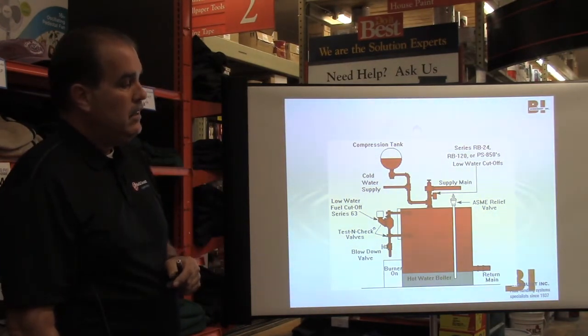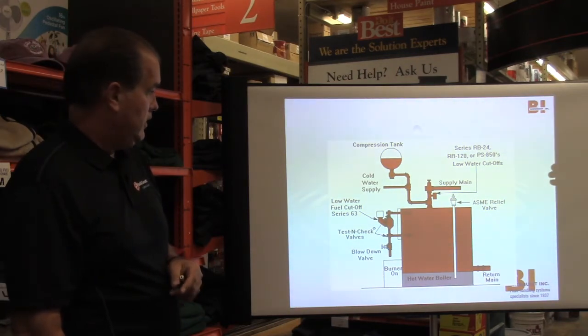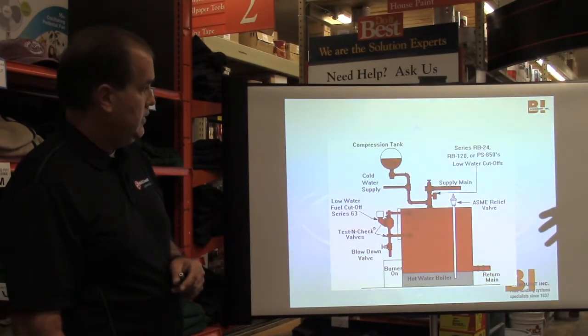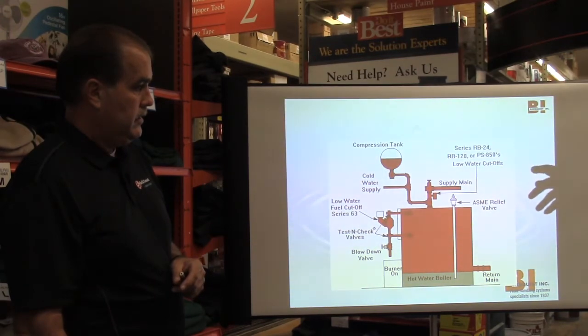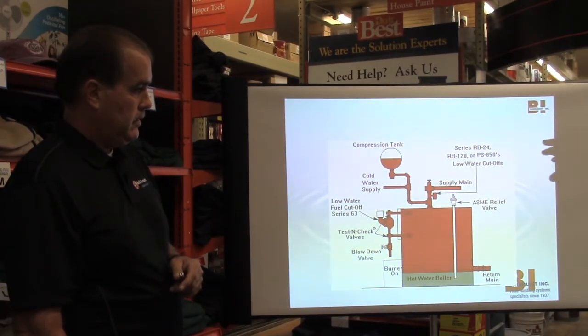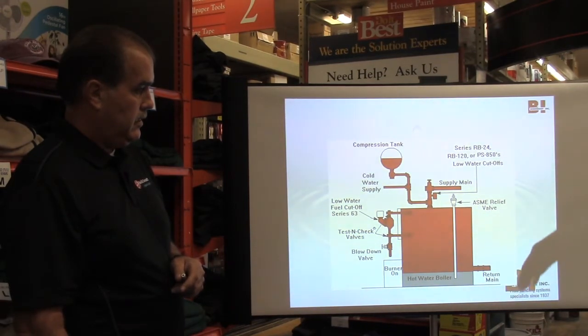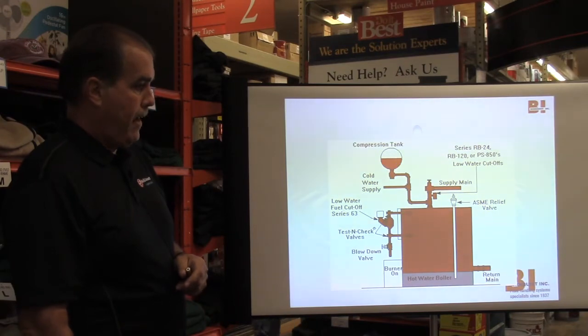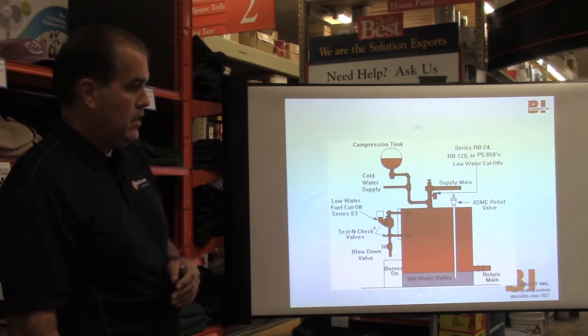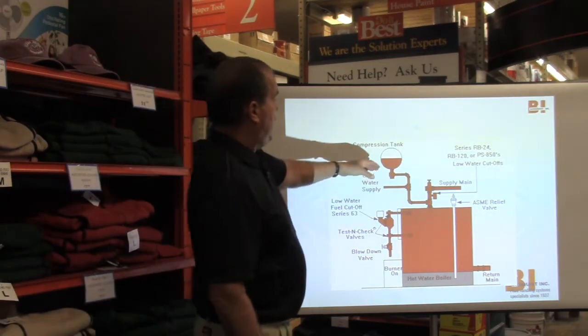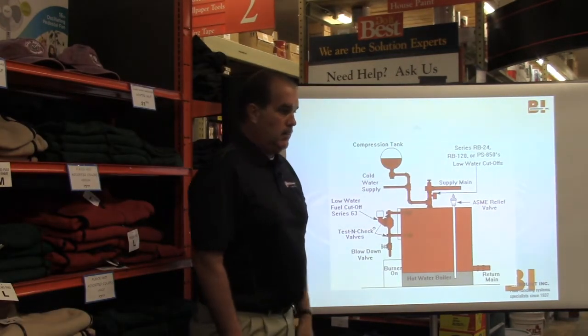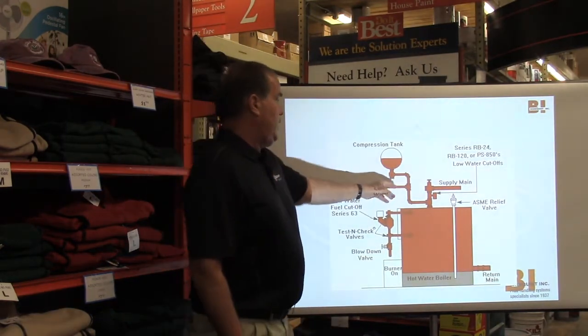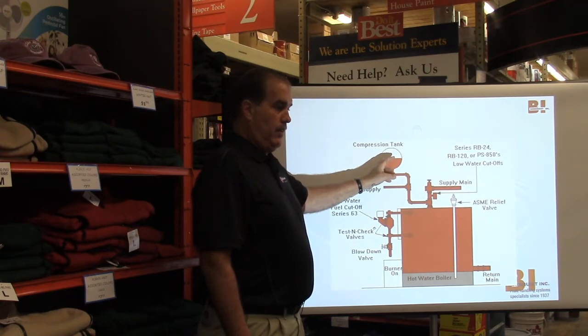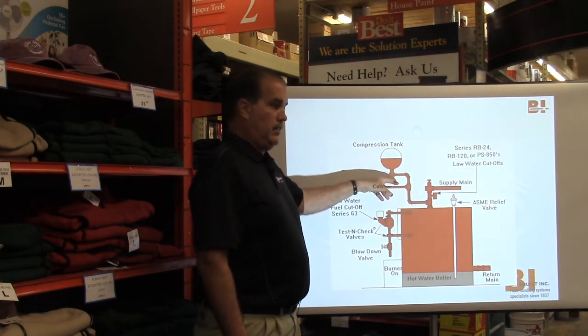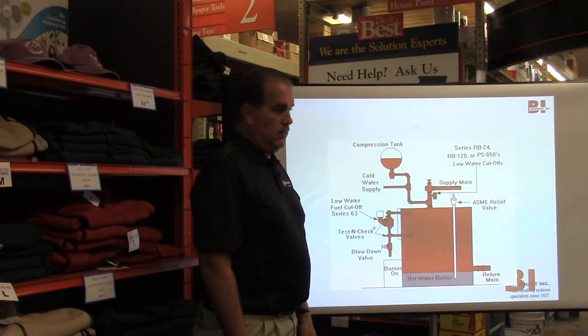Now, let's say I drain all the water from it, and of course I shut down the whole water supply and drain it completely. Then when I open up the water supply, and the water is drained in the tank, the water goes back into the tank. I can hear it. Yeah. That's normal? I thought something was wrong. No. The tank typically is going to be about half filled. That's okay. That's designed, and you might have a fitting that Bell & Gossett makes that allows water in, and it also allows it out. It's not easy to drain this thing.